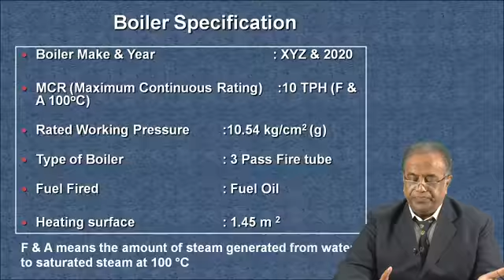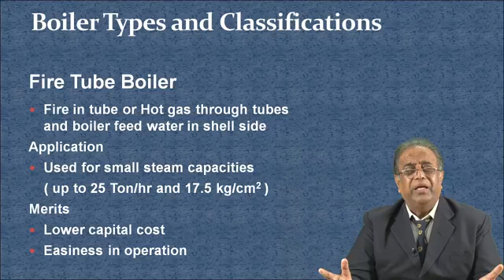Now, boiler type and classification. There may be a fire tube boiler. When you consider a fire tube boiler, it means fire in tube, or hot gases through tubes, and boiler feed water on the shell side. Application: used for small steam capacities up to 25 ton per hour and 17.5 kg per centimeter square gauge pressure. Its merits are low capital cost and easiness in operation.